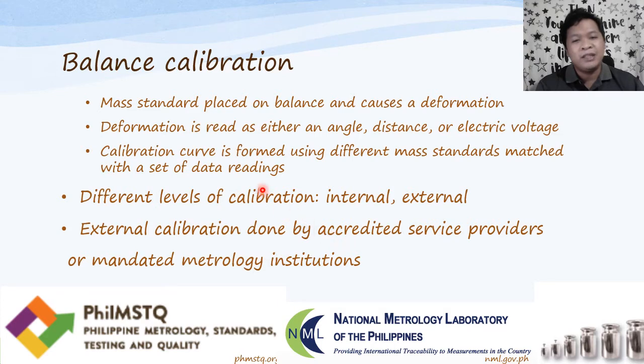Okay. Typically, you have internal and external calibration. So for example, sa laboratory natin, most analytical balances would have a self-calibration procedure, but you can also use an external, so yun yung internal, no? You can also have ikaw yung magka-calibrate na maglalagay ka ng calibration weights dun sa analytical balance. Although usually periodically, meron ka ring tinatawagang outsiders na accredited calibrators to periodically check the calibration of your balance on top of the balance's own calibration system, and you as the end user calibrating it using your own lab calibration weights.